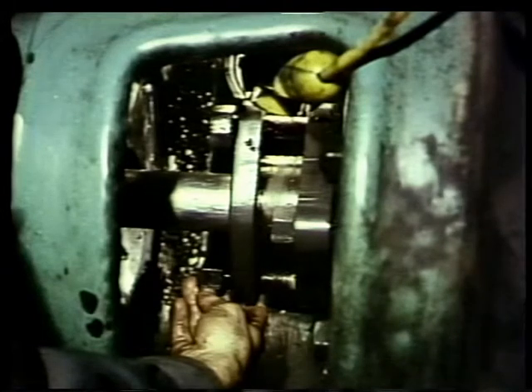If everything is in order, a final adjustment is made to the packing by tightening the gland follower. There should be a minimum of leakage without any signs of heat buildup. But you're not quite done yet. Only after you've made sure that the work area is clean, free of tools, oil spills, and other job hazards, are you truly finished with the job. That's it. The compressor's repaired and back on the line, supplying compressed air wherever it's needed in the plant.